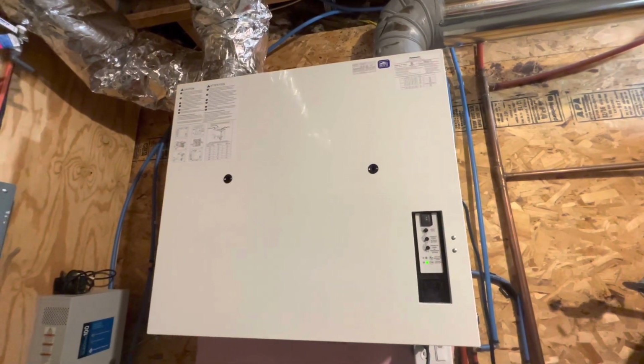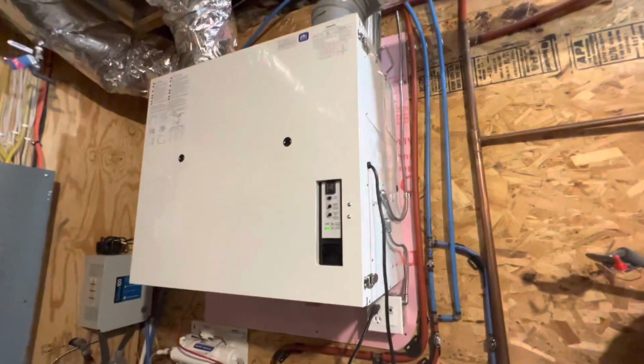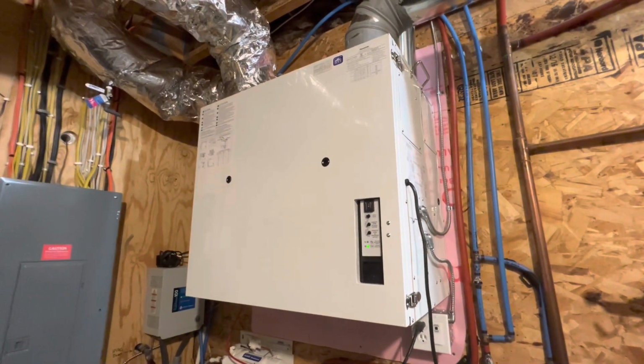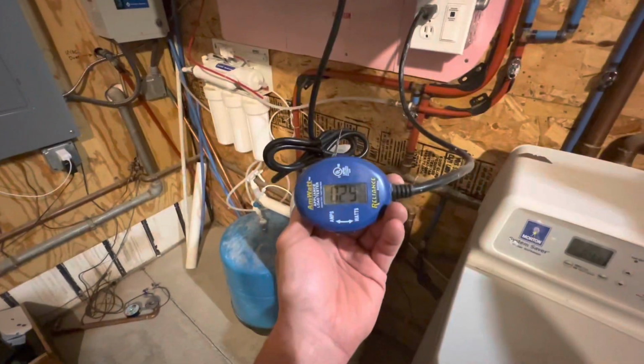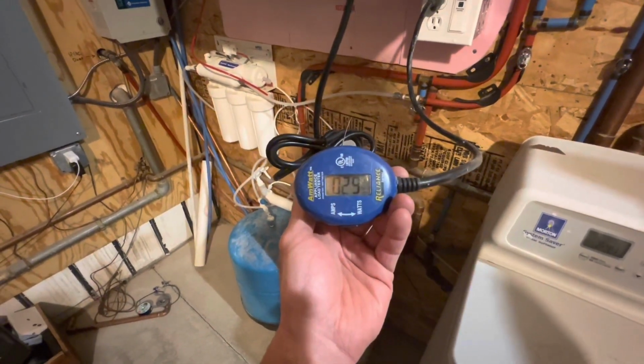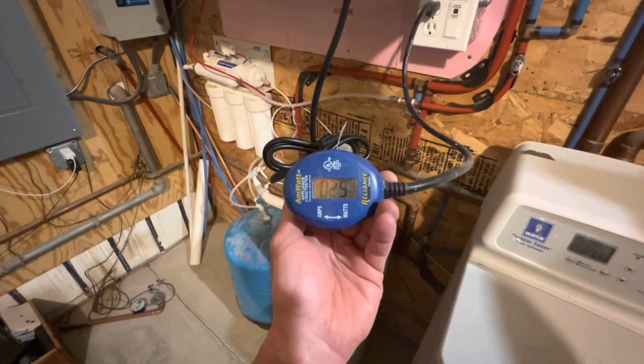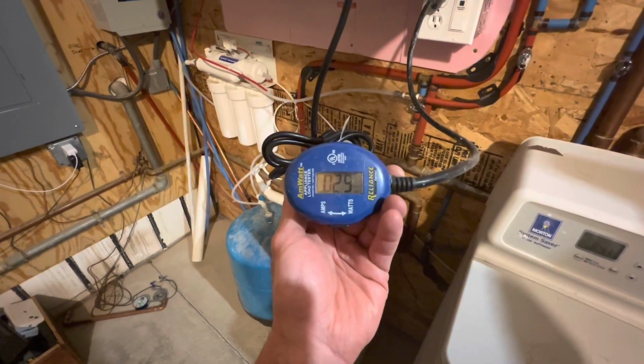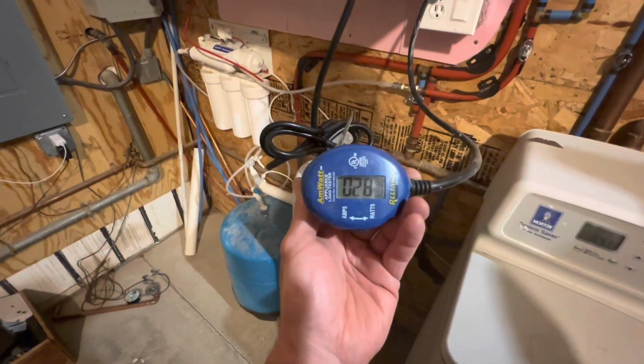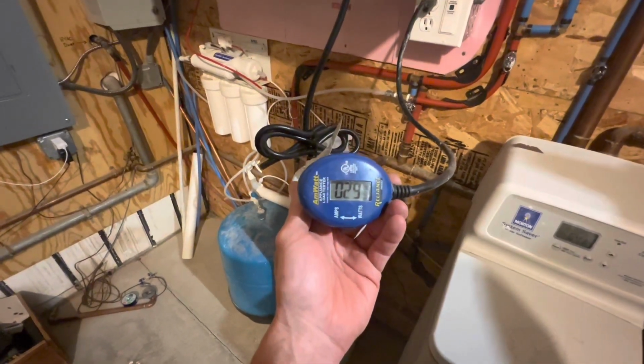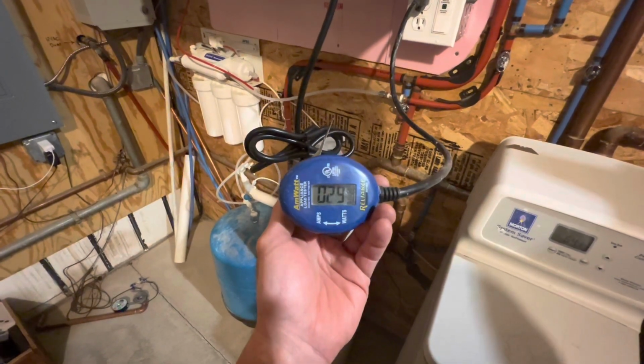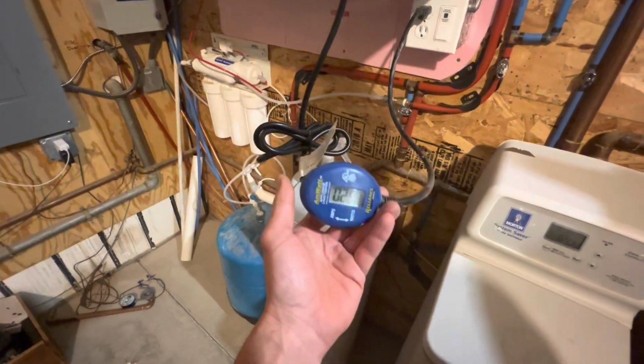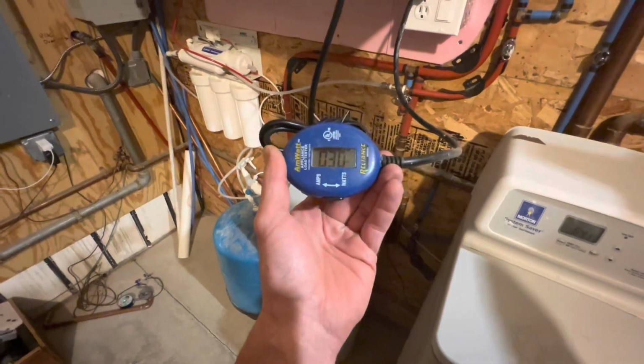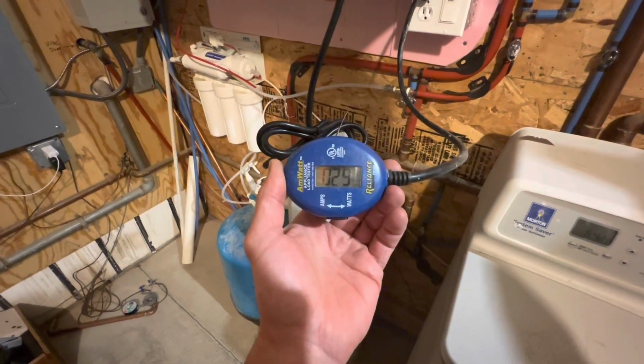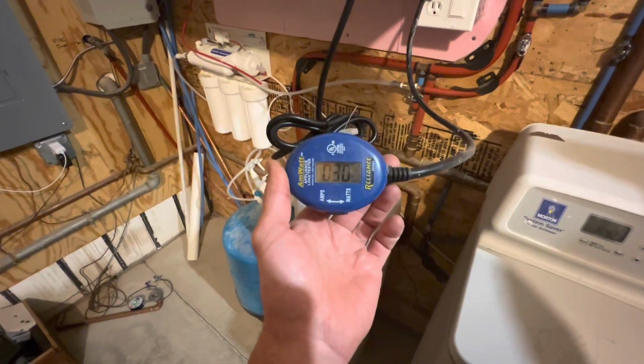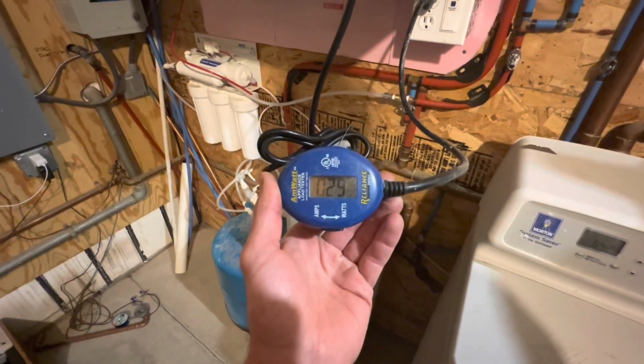So I guess I'll start with overall, I really like the unit. It's very quiet, very low power consumption. Right now I'm running it at 80 CFM on the supply and 60 CFM on the exhaust. I'm running that 20 CFM differential just to keep positive pressure on our house, try to keep the dust out. And you can see it's running right around the 30 watt range, which equates to about $2 a month. I run it 24 hours a day.